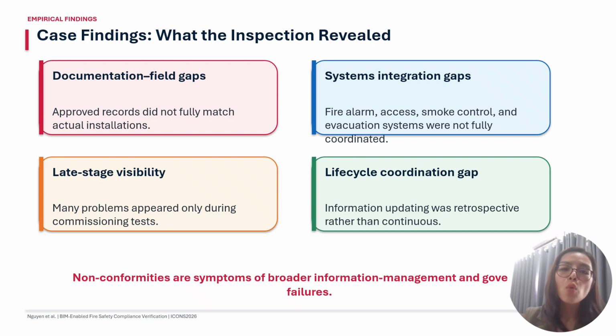The key findings from the inspection review: documentation gaps, where approved records did not fully match the actual installation, and system integration gaps, where fire alarm, access, smoke control, and evacuation systems were not fully coordinated. Late-stage visibility: many problems appeared only during commissioning tests. Life cycle coordination gaps: information updates were retrospective rather than continuous. So non-conformities are symptoms of broader information management and governance failures.